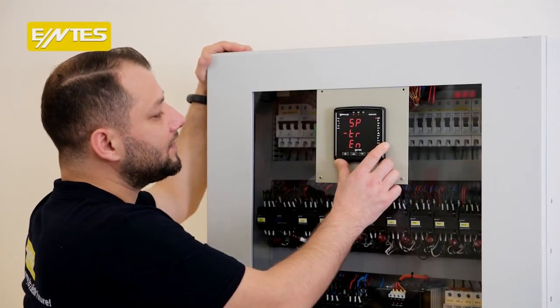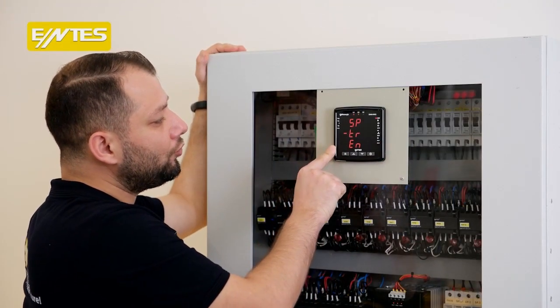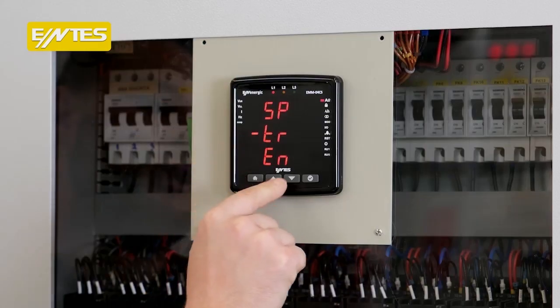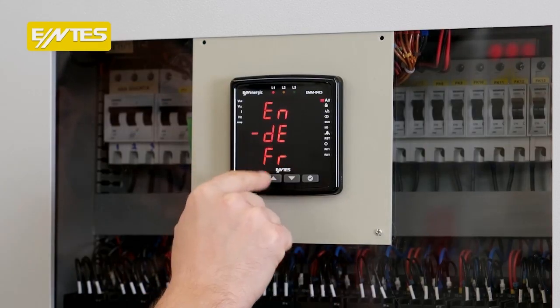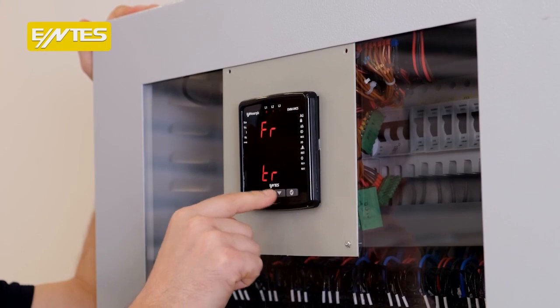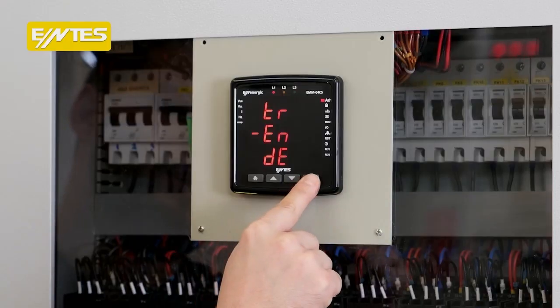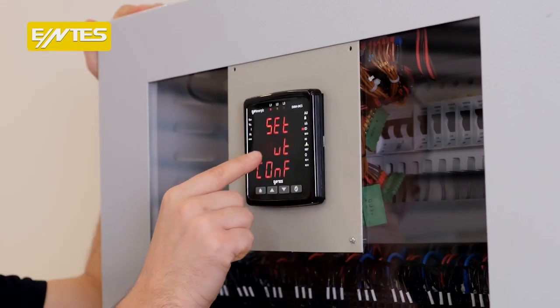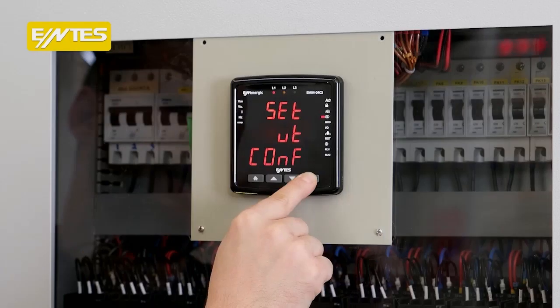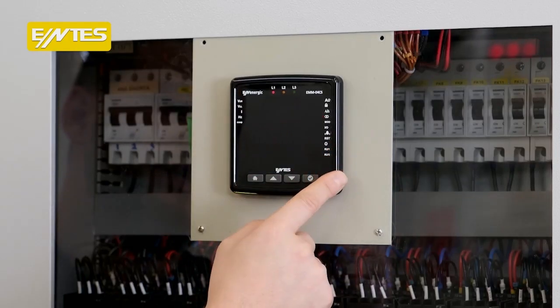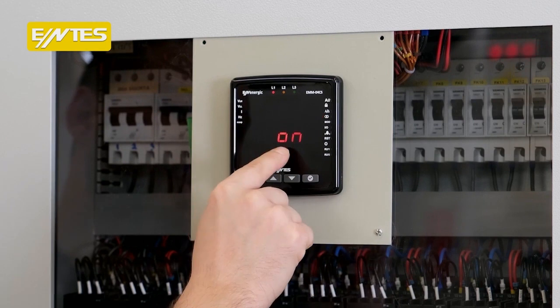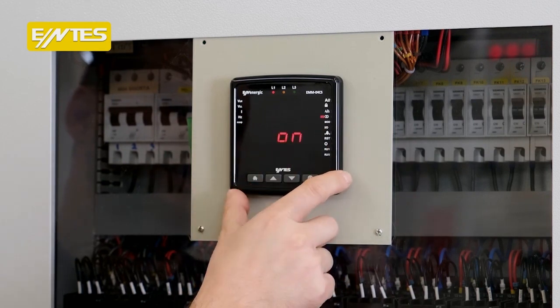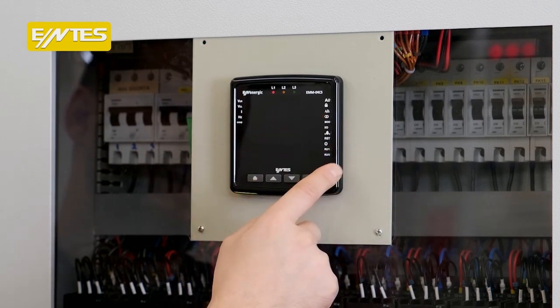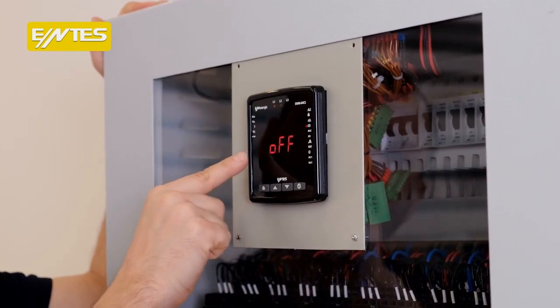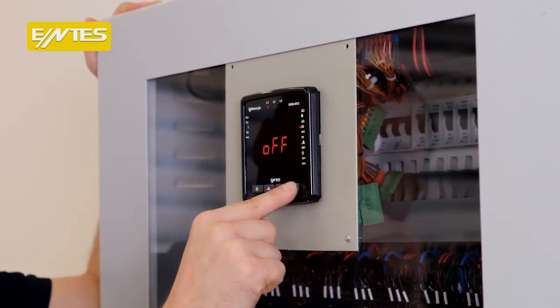Product energized. Installation started. It supports 5 languages for our customers: Turkish, English, German, French, and Spanish. We press the OK button, we confirm. Select the VT setting here, the voltage transformer setting. In the next steps, we input the primary and secondary of the transformer. We confirm the off option because we do not use a voltage transformer.